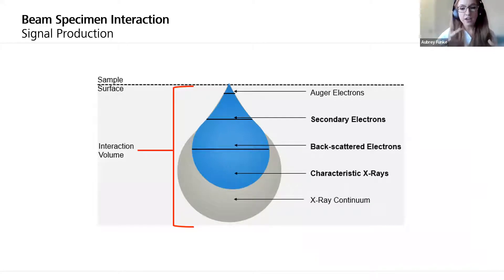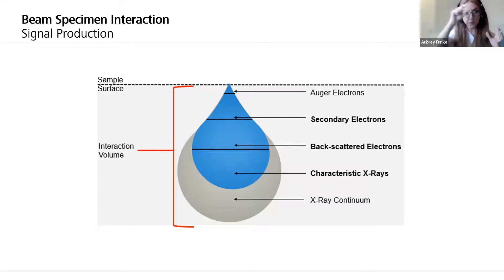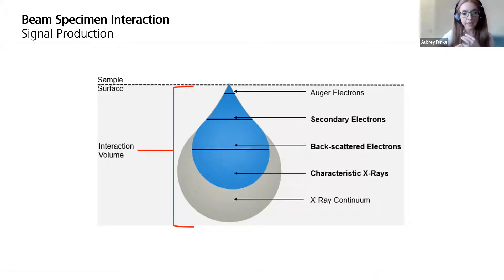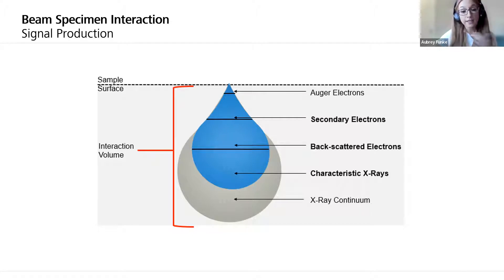As that beam electron interacts with the specimen, different signals are produced. In order to visualize the specimen in the SEM, you're going to choose one of these signals with your detector, and that will change the way that image looks on screen. The various signals that are collected include visible light, heat, x-rays, and different types of electrons like Auger electrons, secondary electrons, and backscattered electrons. We're going to focus on secondary electrons and backscattered electrons, as these are primarily used to create that visible image.